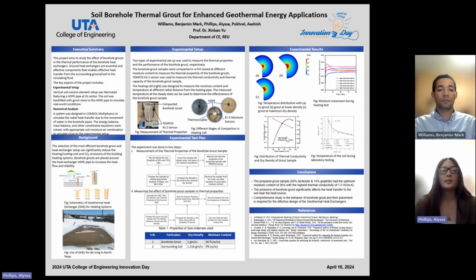The second step consisted of testing and measuring the effects of the borehole grout, such as heat flux, temperature, and moisture movement. We compacted borehole grout with 36% moisture content and soil with 9% moisture content in 6 layers around a heat source. We placed sensors in the third layer along the radius and ran the heat test.